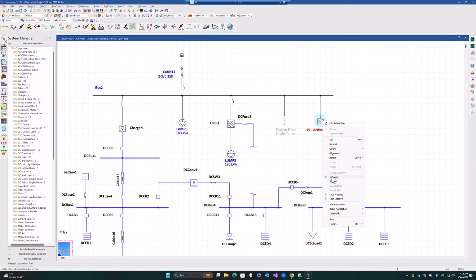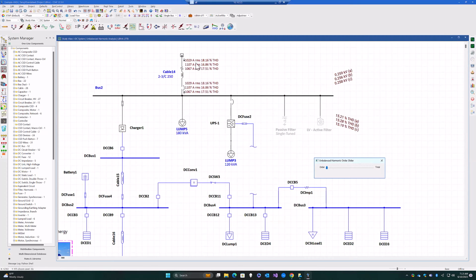In the case of unbalanced harmonics, we can put this filter out of service and run our harmonic simulation, so we can see we have some amount of unbalanced harmonics as well as heavy distortion in the system. First, let's turn on our passive filter so we can see what happens when you have a passive filter in the system. We'll create an output report for a passive filter and run our simulation, so we can see that we dropped our distortion down to 12% by having a passive filter. Very quickly, if you did not have one, it was 18%, just as a frame of reference. So with the passive filter tuned, we can go to about 12%.